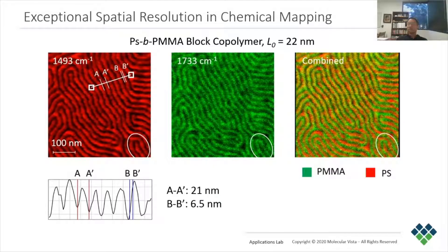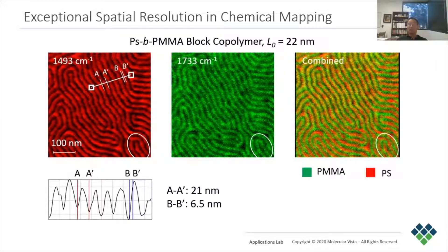To determine the spatial resolution, we use a block copolymer which has a well-defined distribution of chemical components. In this PS-PMMA block copolymer with a full pitch of 22 nanometers, each chemical component is about 11 nanometers wide. When we set the excitation laser to 1493 wavenumber, which is a strong PS absorption band, PIFM highlights just the PS molecules shown in red. When we repeat the measurement at the same location with the laser set at 1733 wavenumber, PIFM highlights the PMMA molecules in green.